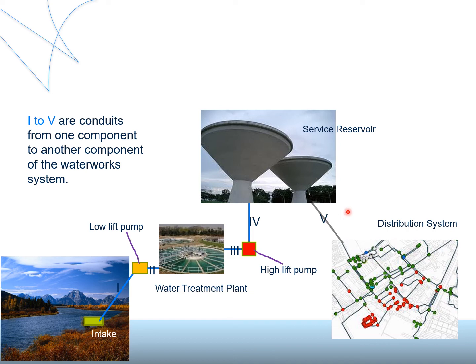So the distribution system should be designed for peak hourly demand because it needs to handle the peak hourly fluctuation in the demand. Now, the service reservoir is mainly to balance the fluctuation of the demand in the distribution system. For the 24-hour fluctuation, it has some storage capacity, and the amount of water in the service reservoir fluctuates with the demand in the distribution system.